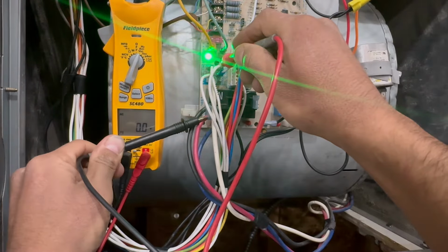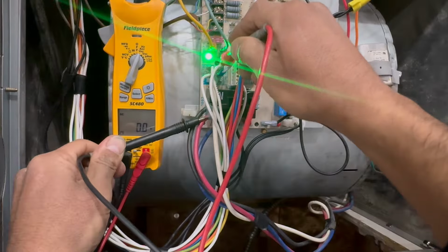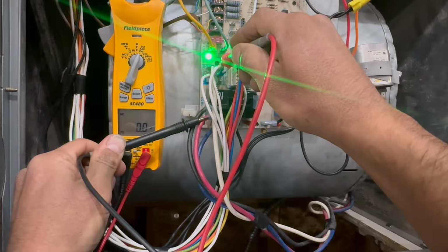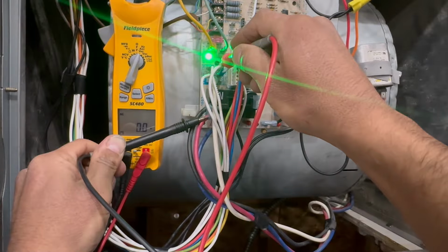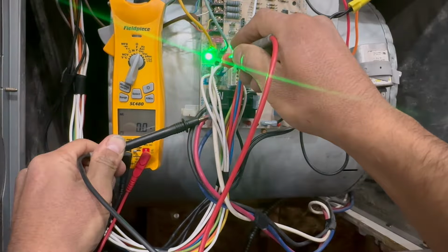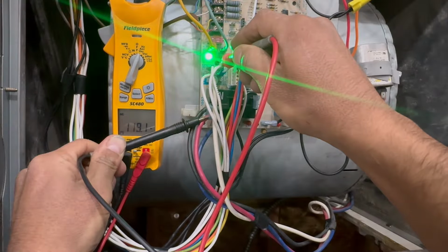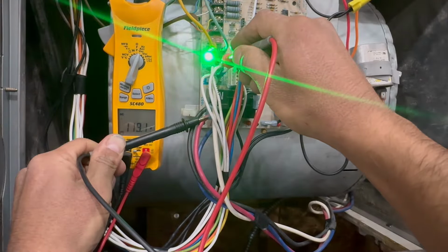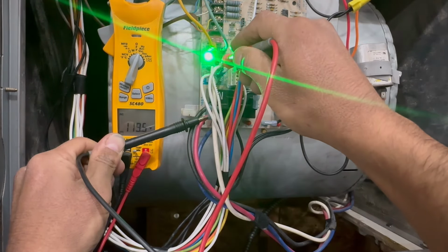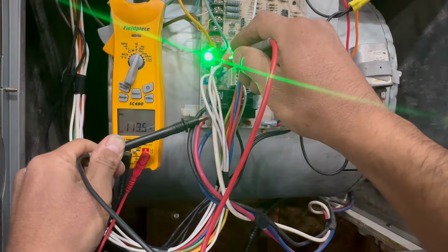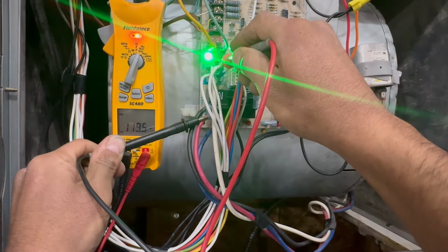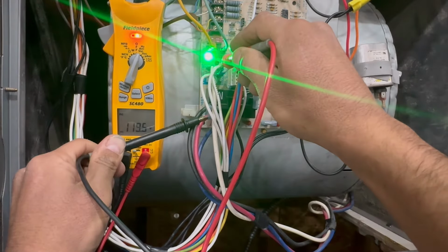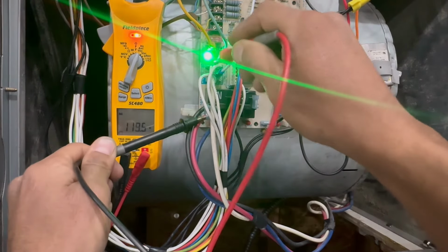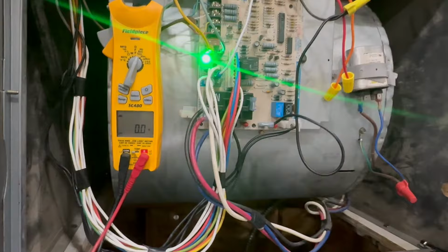But let's see. I'm putting the wire in, and I'm checking the neutral. It hasn't sent out 120 volts yet, right? So it's going to make sure that area and the heat exchanger is warming. You see, now it turns on the blower motor. So if you go to a job and your blower motor is not turning on, you checked your capacitor, well, check if your board is actually sending 120 volts. And you check it once again by doing what I just showed you.